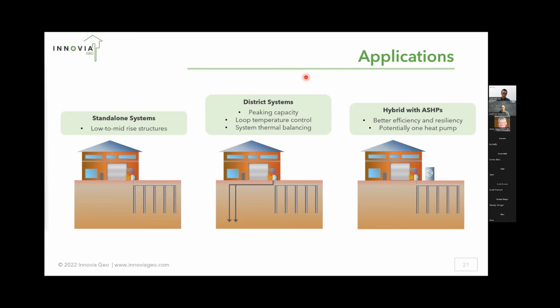A challenge with conventional geothermal systems in our climate, in high rises, is that the buildings tend to be cooling dominant, which is a little bit counterintuitive considering the winters we have. But with heat rising and a lot of the building practices using a lot of glass for high rises, there's a lot of heat accumulation within those buildings, and also with the density of folks in there. And so there's a need to dissipate excess heat in order to have the system balanced through the year. So we're looking at using our technologies as a way to help balance and maintain that temperature control.